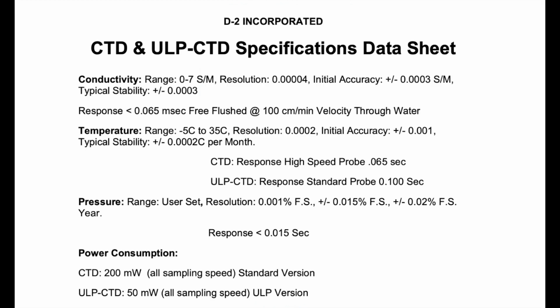This is the specification data sheet for the CTD and for the ultra-low power version of the CTD that we offer. The ultra-low power version has a lower hertz, however it can operate well below 50 milliwatts. The CTD has a conductivity range of 0 to 7 Siemens per meter, an initial accuracy of 0.0003 Siemens per meter. This accuracy and its typical stability allow us to offer full ocean depth measurement with our conductivity cell, as this rivals the accuracy of any other closed field conductivity cell in the market.